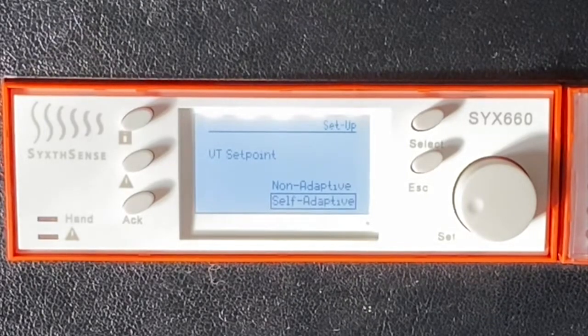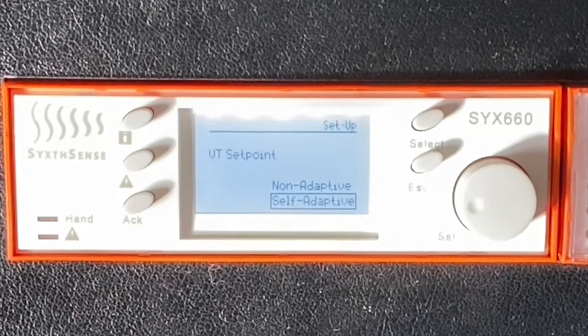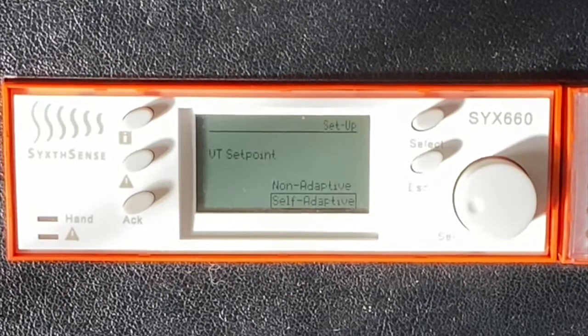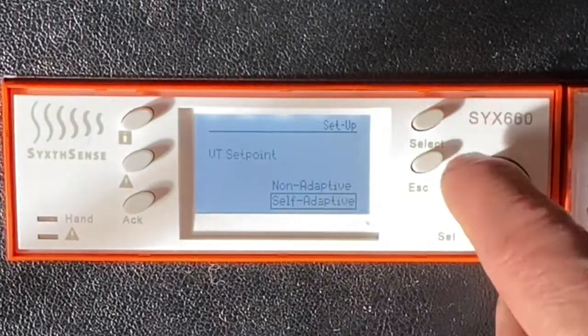So if the room set point was 20 degrees and the current room temperature was 18 degrees, we would be in deficit of 2 degrees. With the room influence ratio default setting being 3 degrees, the 2 degree deficit would be multiplied by the 3, and we would add 6 degrees to the current calculated flow set point. This provides some additional comfort and some additional boosted heating to the radiators, so that we get a little bit more faster reactivity to the deficit in space temperature. Okay, so we're going to choose self-adaptive.